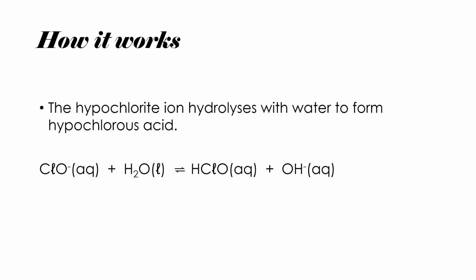Now, these salts, when they dissolve in water, produce the hypochlorite ion, which is what we need for our disinfection. So the hypochlorite ion in turn will hydrolyze with water to form hypochlorous acid. So remember, this is our principal bactericide and algicide. So this is the most effective oxidizing agent. Even though this one is a good oxidizing agent, it's not as good as this one.